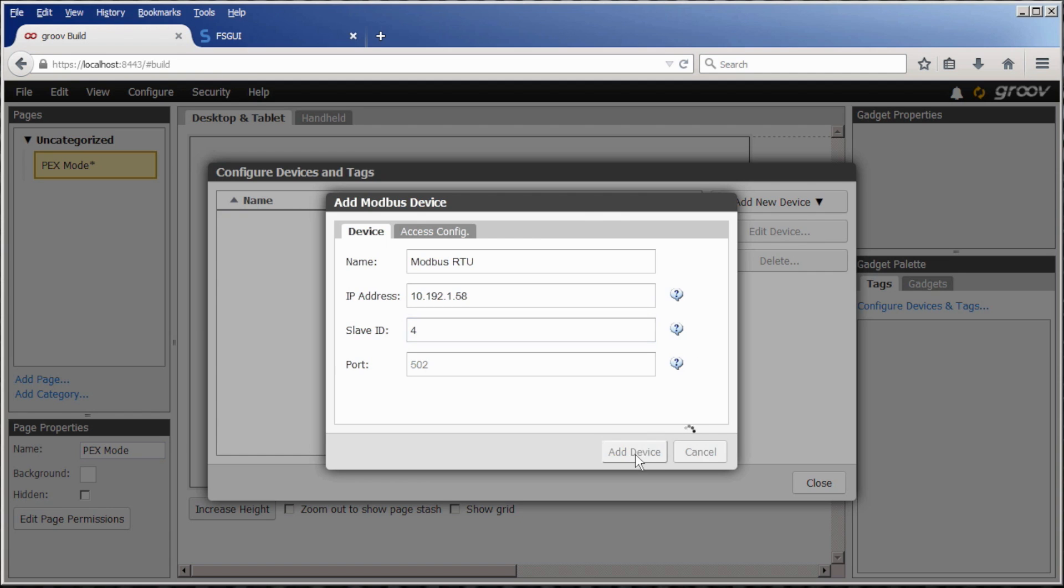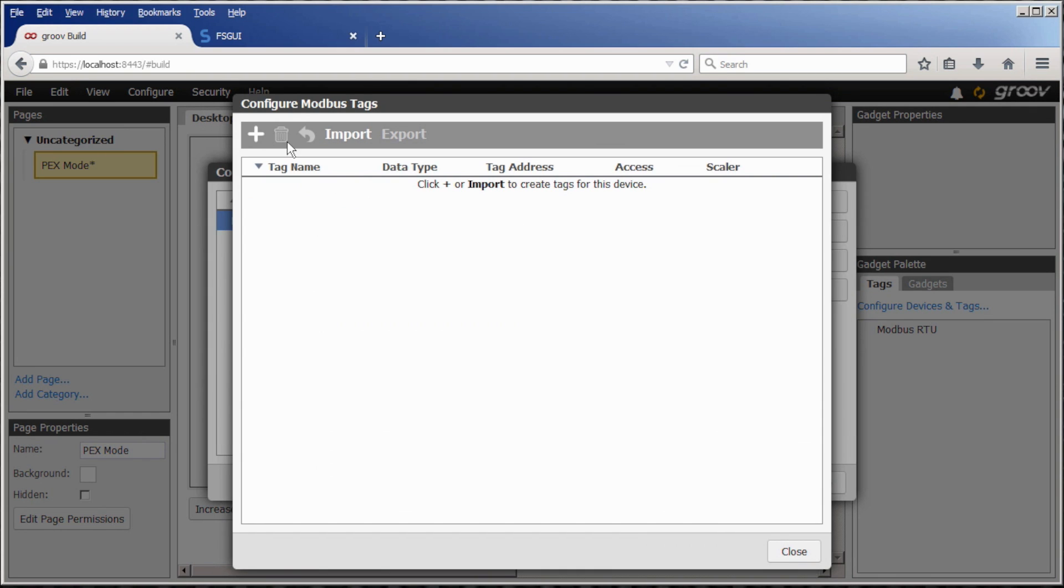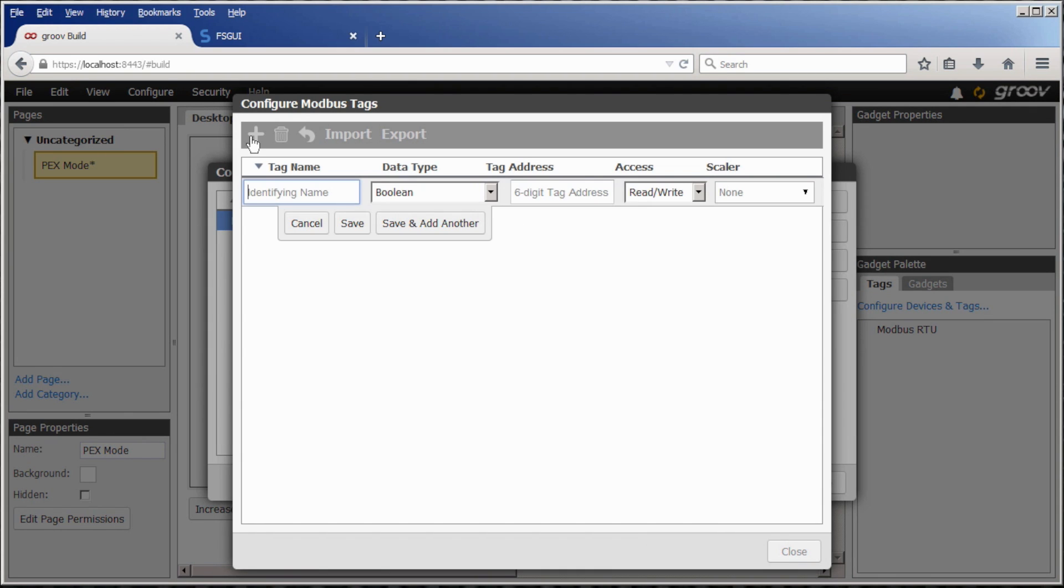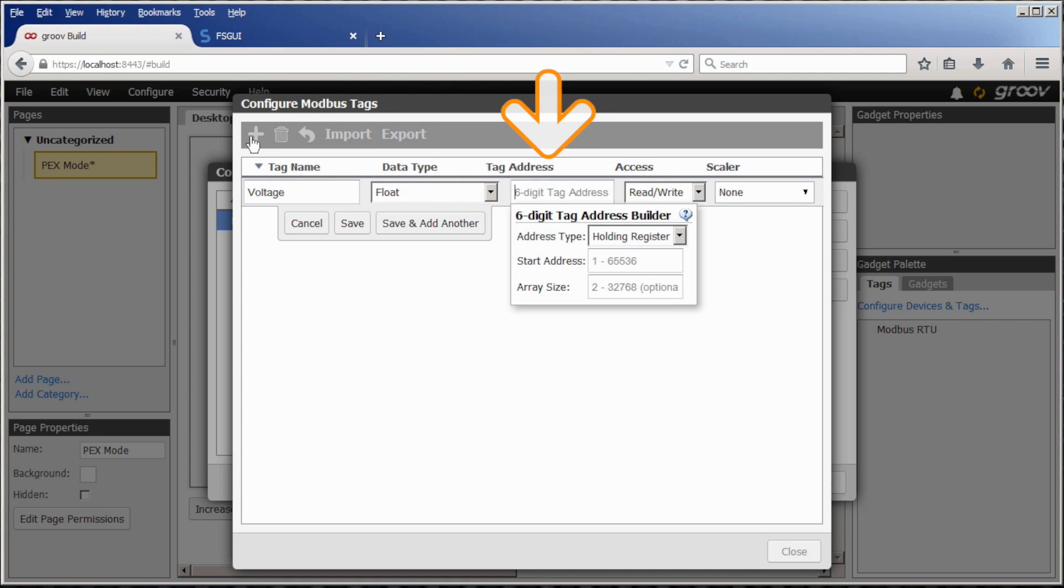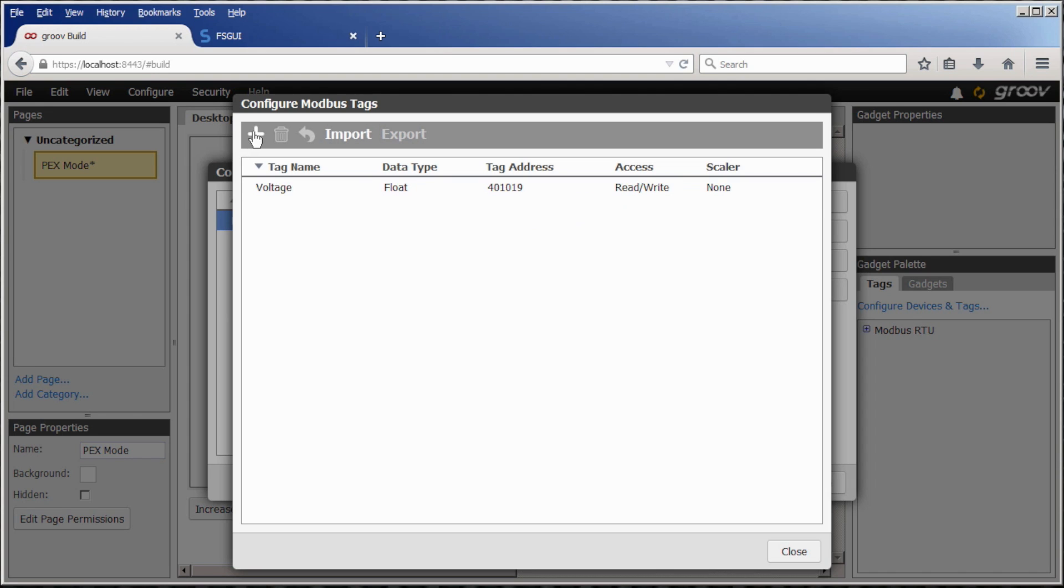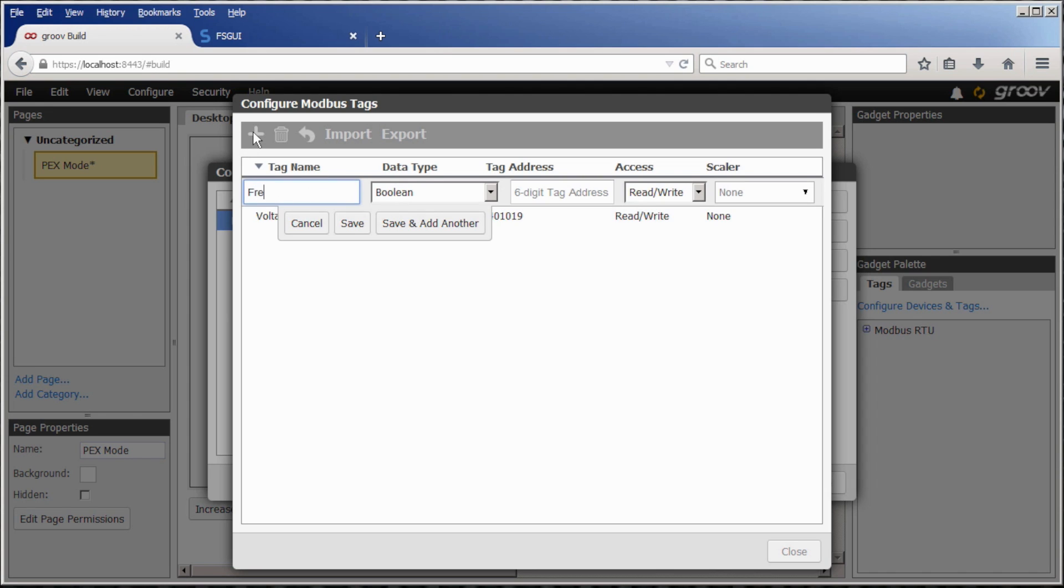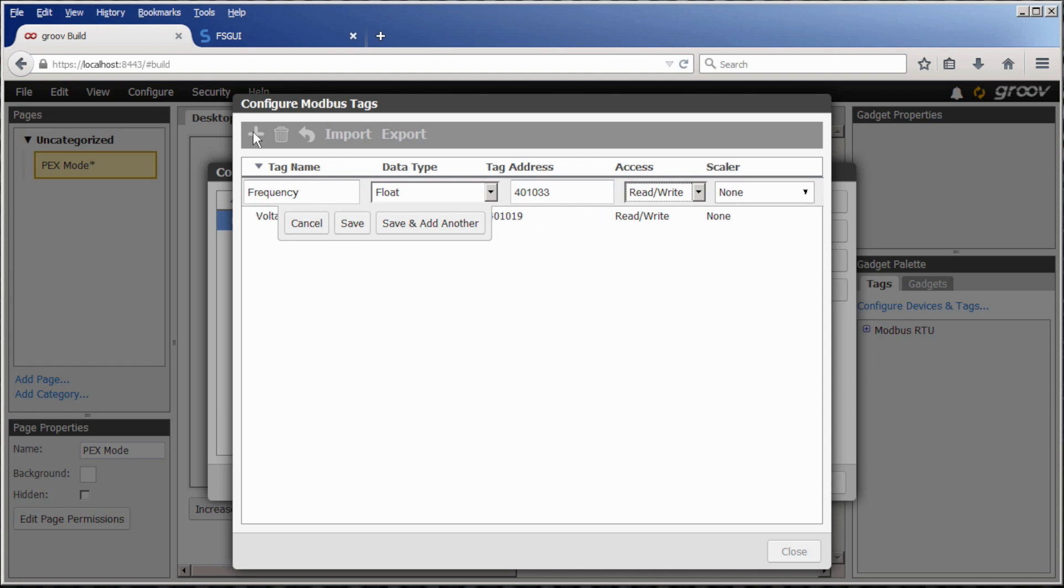Now we want to add the tags for voltage and frequency. Go to configure tags and click on the little plus sign in the top left. I'll name this first one voltage. It's a float data type, and its start address is 1019. Groov knows how to correctly address the tag based on its type and will auto-complete the tag address to the 400,000 value you see there. Now click save and repeat this for any other tags you wish to add to your Groov. I'm adding a second tag for frequency, but you can add as many tags as you need.